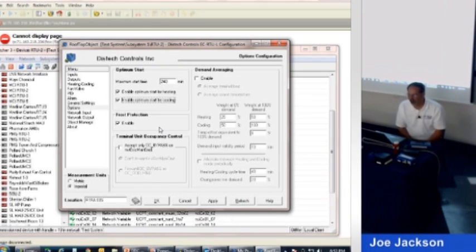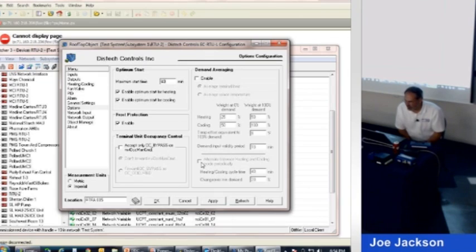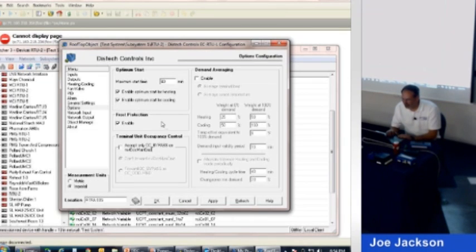If the start time is 7 o'clock in the morning and you don't want it to ever start more than an hour early, there you go. It'll never start more than an hour early. Frost protection, that just says if some crazy person comes in and sets the thermostat at 20 degrees, it isn't going to matter. When it hits 38 degrees, it's bringing the equipment back on regardless of what the set point is. It's just to keep an operator from screwing up too bad.